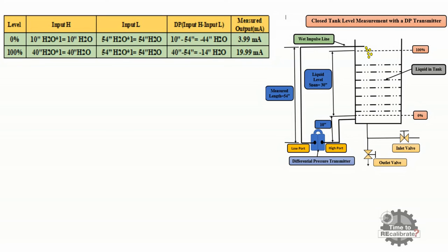At 100% level, the DP transmitter high side has 40 inches H2O pressure, multiplied by the specific gravity of water. Here, 40 inches is the total distance from the transmitter to the 100% line. So the high input side has 40 inches H2O at 100% level. Similarly, the transmitter low side has 54 inches H2O pressure, multiplied by the specific gravity of water which is 1, giving 54 inches H2O. Differential pressure is 40 minus 54, which equals minus 14 inches H2O at 100% level.